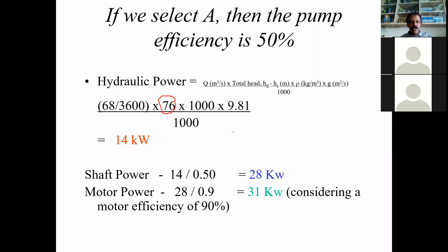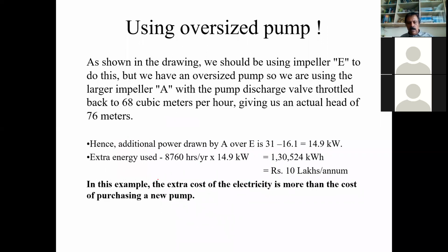So this change has led to an increase of almost 50%. Now the pump is drawing 31 kilowatt. Everything else remains the same. Now what is the impact? If you see, the life of the pump is about 20 years. Now what will be the impact of this oversized pump?